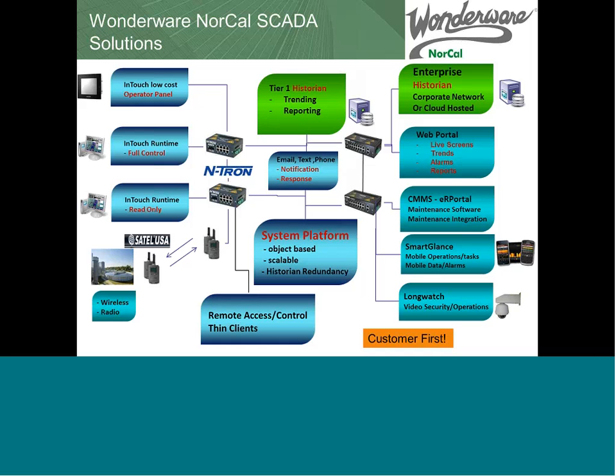We have traditional InTouch, which is the world's leading HMI we'll talk about. That allows you to do your monitoring of your plant and equipment and control. So you can actually change set points, turn things on and off, acknowledge alarms. We also have InTouch read-only, for folks that don't have authorization or need to control the plant, to turn things on and off and change set points, but want to be able to monitor.